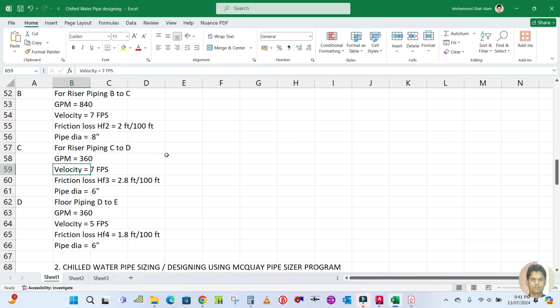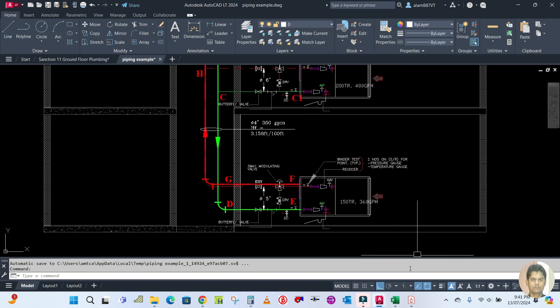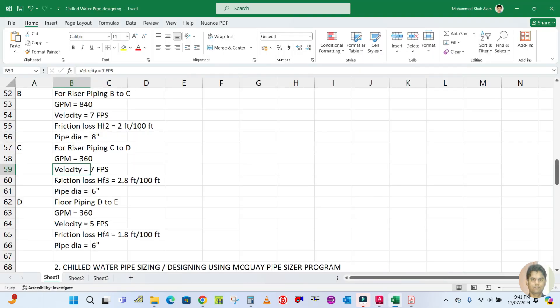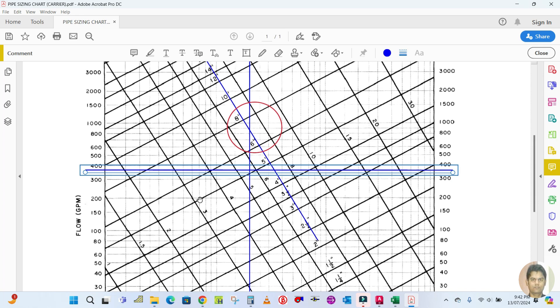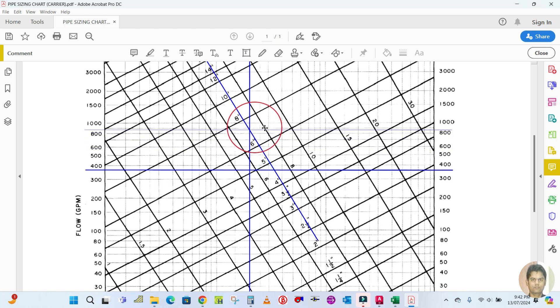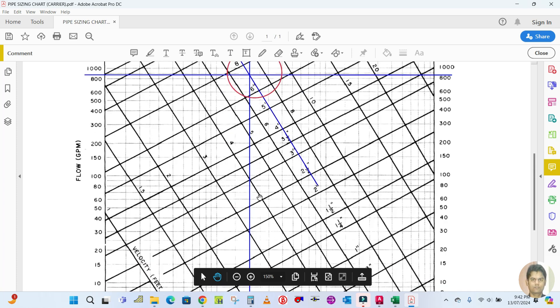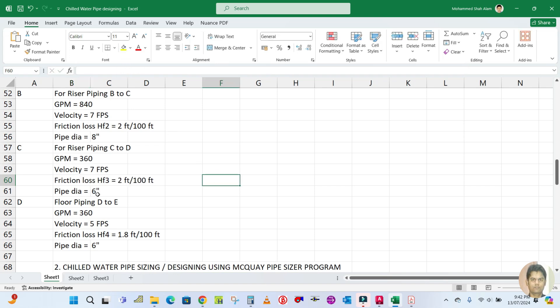For riser piping C to D, the velocity is again 7 feet per second and the GPM is 360. Moving the lines accordingly, the friction loss is again 2 feet of water per 100 feet and the pipe size is 6 inches.